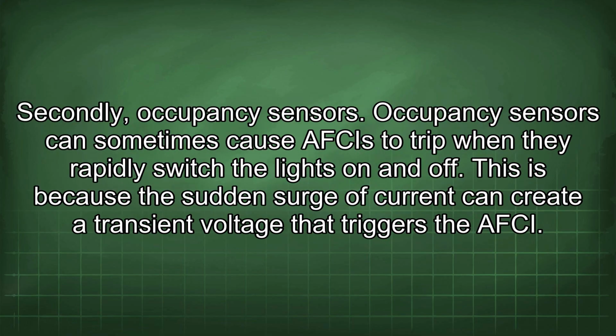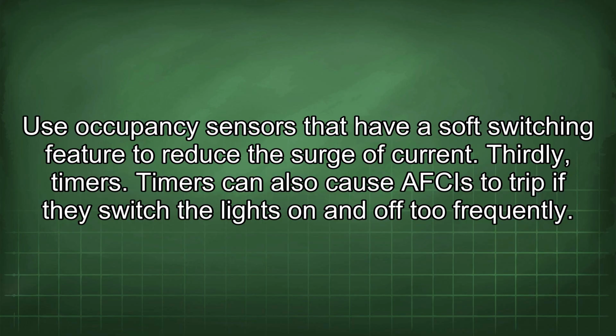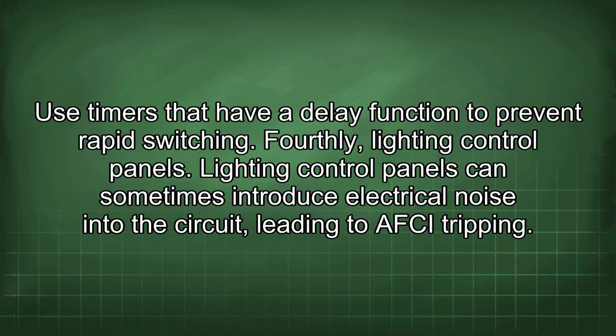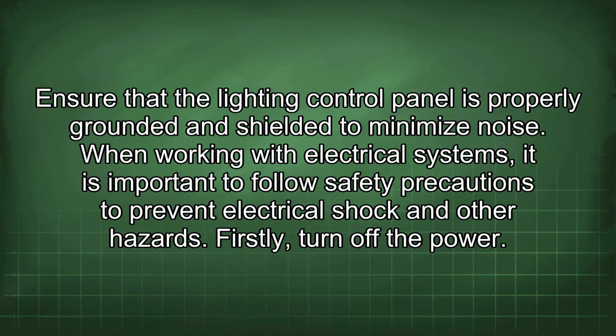Secondly, occupancy sensors. Occupancy sensors can sometimes cause an AFCI trip when they rapidly switch the light on and off. This is because the sudden surge of current can create a transient voltage that triggers the AFCI. Use occupancy sensors that have a soft switching feature to reduce the surge of current. Thirdly, timers. Timers can also cause an AFCI trip if they switch the lights on and off too frequently. Use timers that have a delay function to prevent rapid switching. Fourthly, lighting control panels. Lighting control panels can sometimes introduce electrical noise into the circuit, leading to AFCI tripping. Ensure that the lighting control panel is properly grounded and shielded to minimize noise.